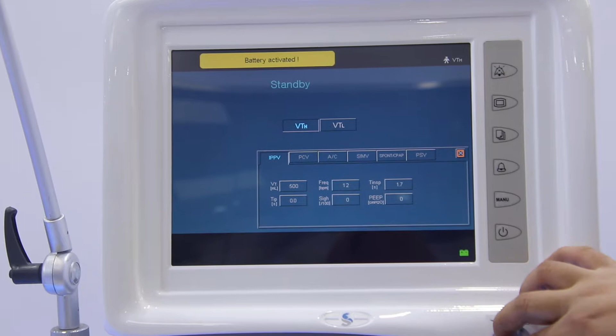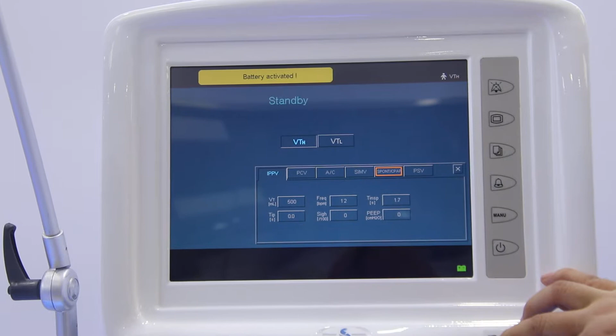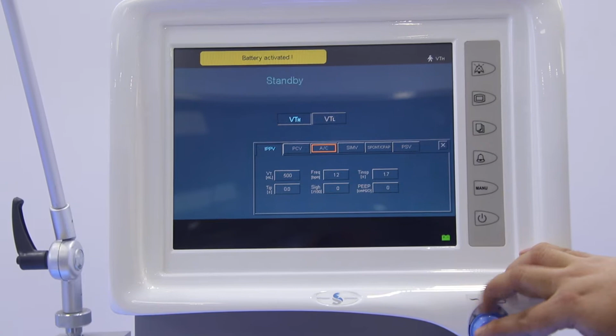Once we press the rotate button, we can choose the ventilation mode first. It includes IPPV, PCV, AC, SIMV, spontaneous CPAP and PSV. So it means our machine has both the volume control and the pressure control modes. You can use it for different patients. And then under each ventilation mode, we can choose different details like the tidal volume, frequency, and IE ratio. Then once we confirm, we will get into the main interface.